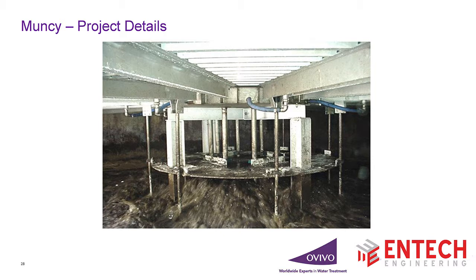Here's a picture of the converted anaerobic digester, and this is the draft tube aerator. And actually, this draft tube, and I've got some better pictures later, is my favorite. It does an excellent job. You can see the violence of the aeration and the mixing pattern it creates. It does a great job.